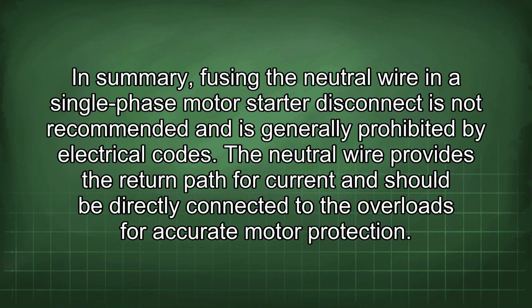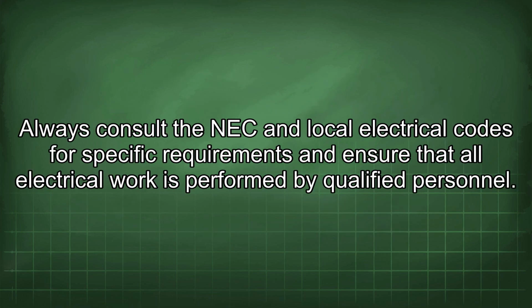In summary, fusing the neutral wire in a single-phase motor starter disconnect is not recommended and is generally prohibited by electrical codes. The neutral wire provides the return path for current and should be directly connected to the overloads for accurate motor protection. Always consult the NEC and local electrical codes for specific requirements and ensure that all electrical work is performed by qualified personnel.